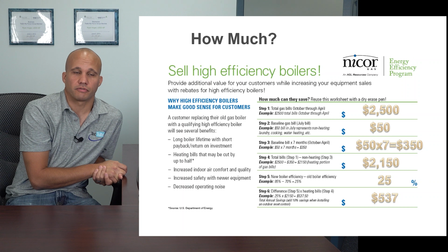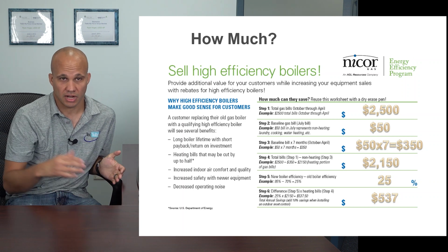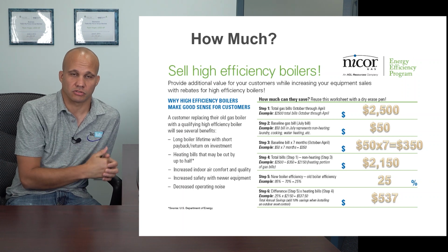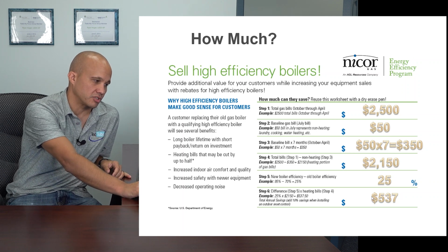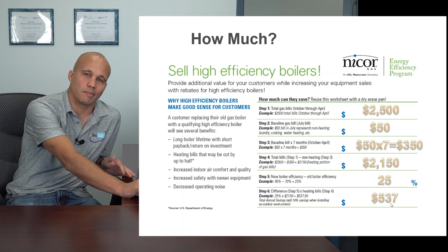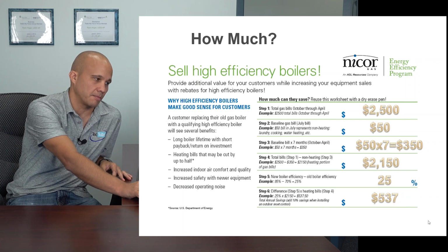If you have an old, inefficient, beastly boiler, then outside air reset has an even better energy saving story because there's more waste, so hence there's more savings. But on a 95% boiler, another 10%, so it's another $50. So about $600 in savings for this particular example.